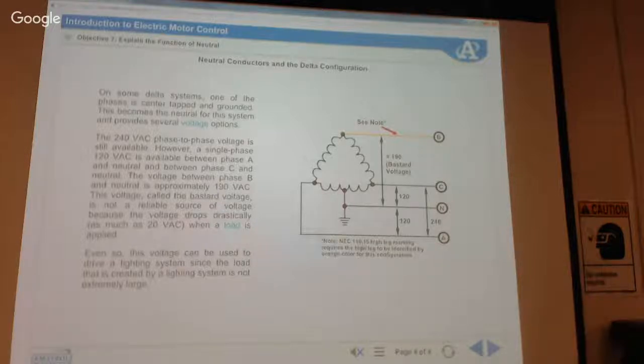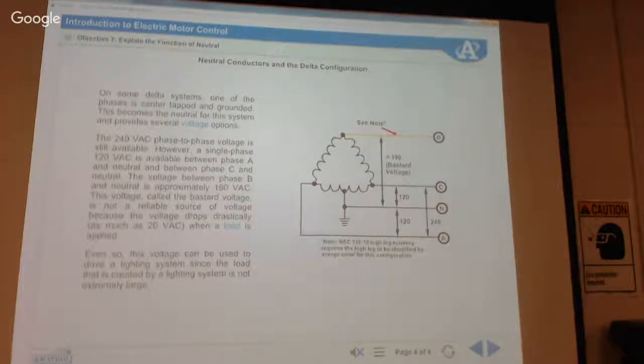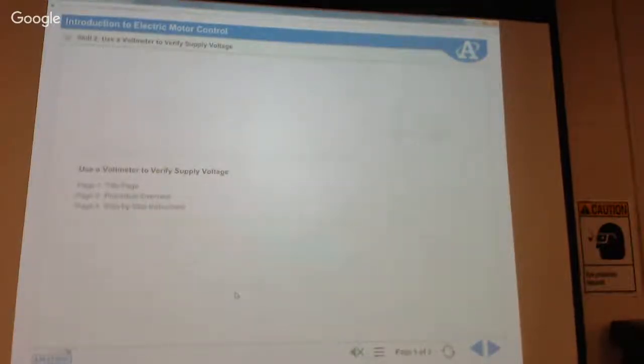And it says, note, NEC 110.15, high leg marking requires the high leg to be identified by orange color for this configuration. Typically, I don't think I've ever seen anybody use it, but you could if you wanted to. Mainly because if you run 190 volts in the plant somewhere, somebody's going to make the mistake of sticking a breaker on that panel and trying to plug in off of it, it'll be bad. If you don't use it, are you wasting anything? No. Okay. This is a distribution transformer.